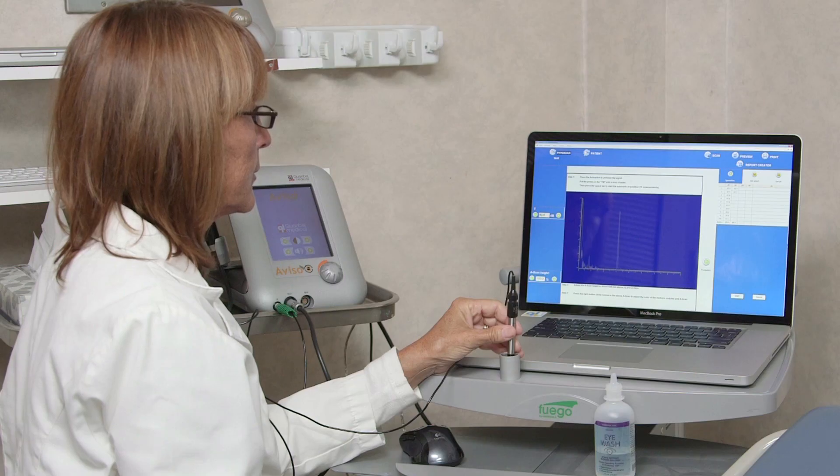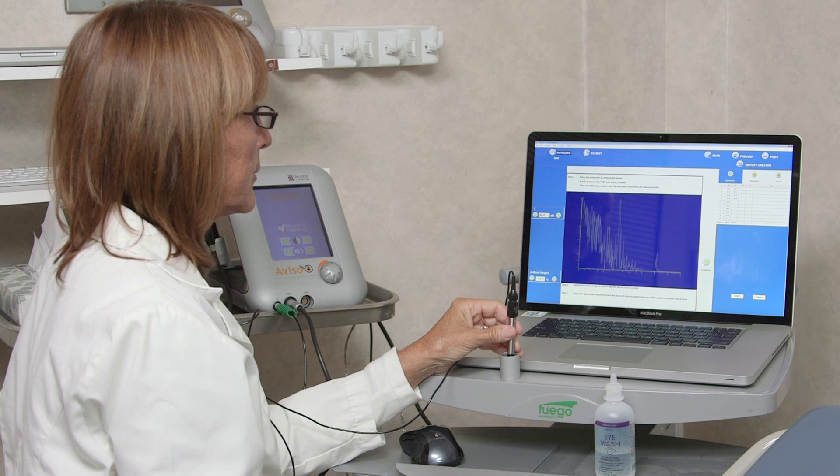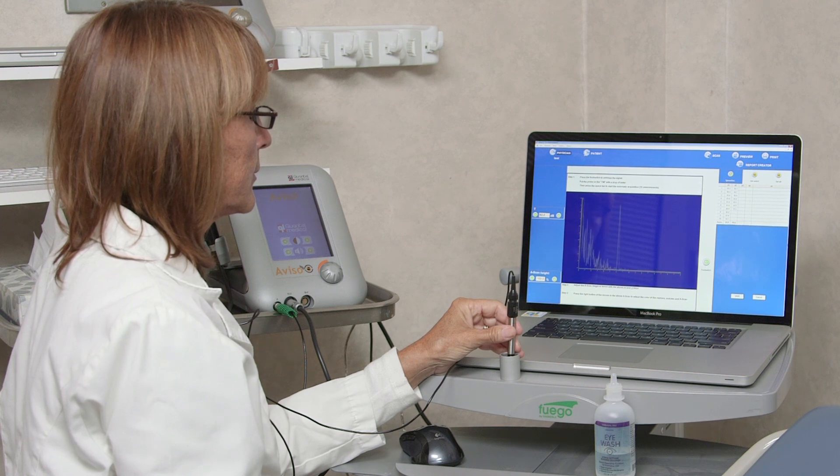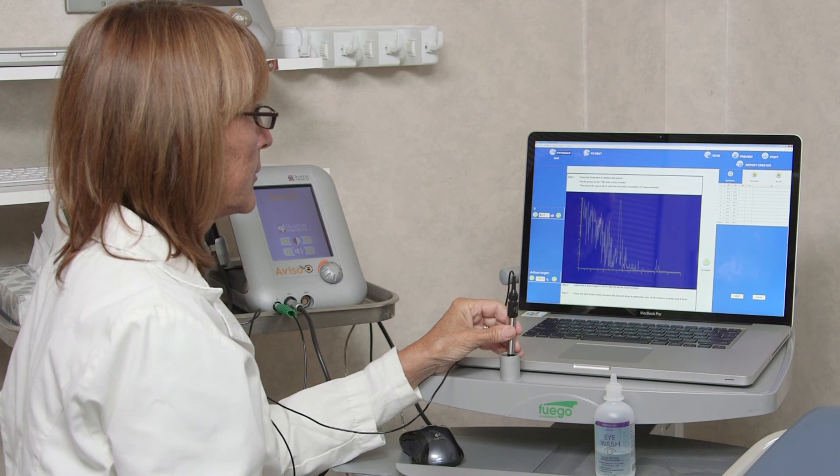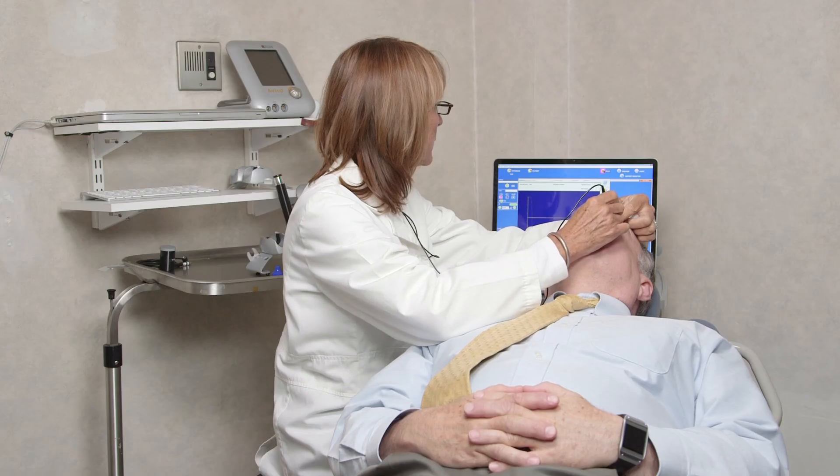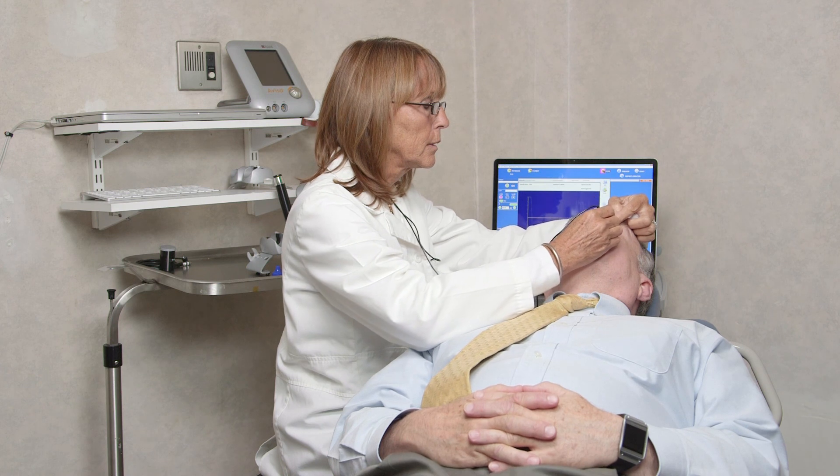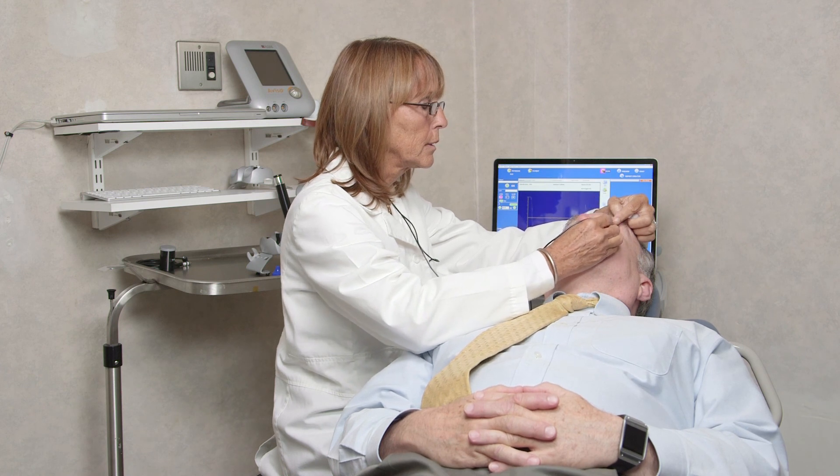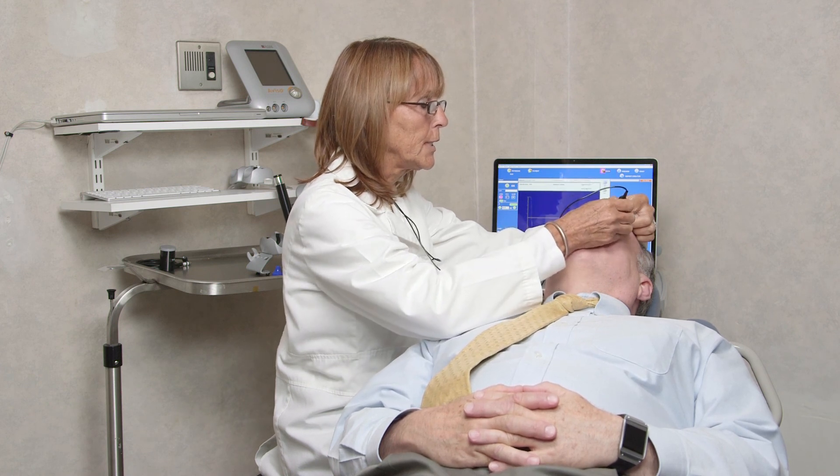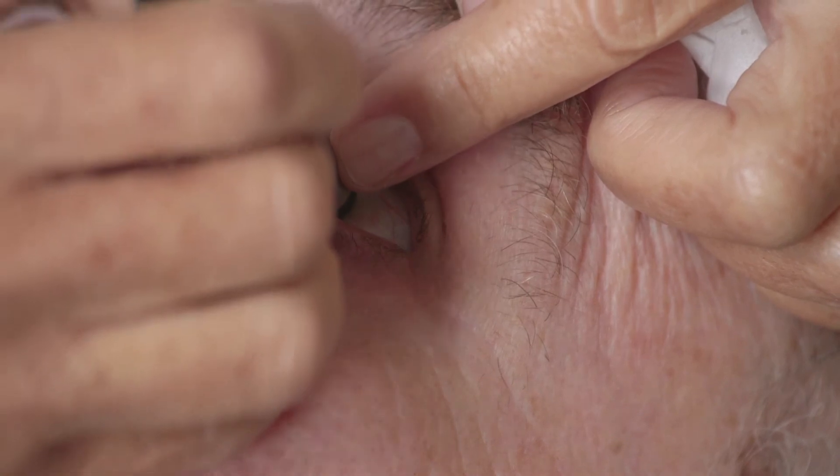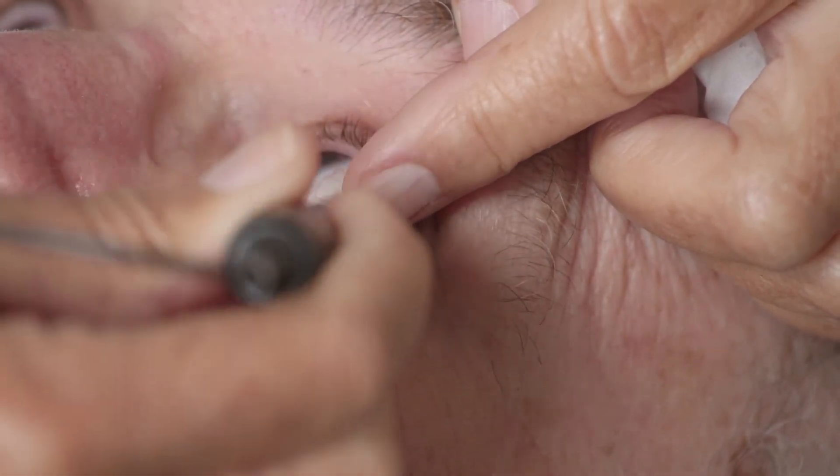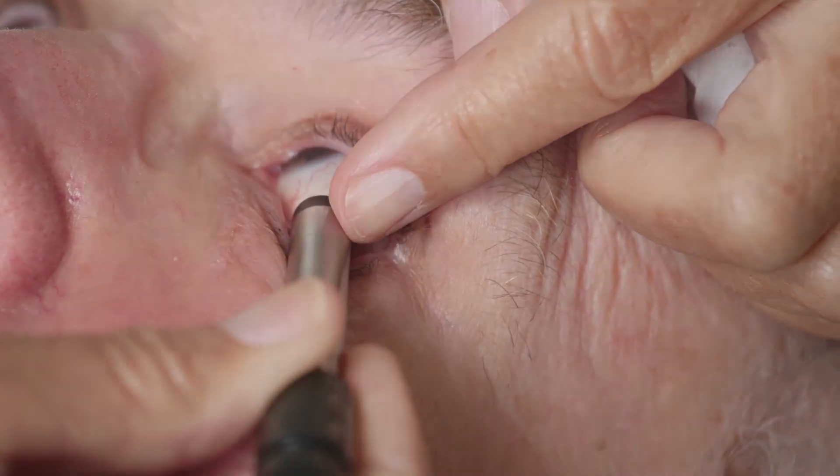Standardized echography refers both to the specific calibration of ultrasound instruments and probes, and to the combination of data derived from both A and B-scans. This information can help in diagnosis, management, and monitoring of therapy. In standardized echography, the qualitative topographic information obtained on B-scan is complemented with precise quantitative and tissue-differentiating information from A-scan.